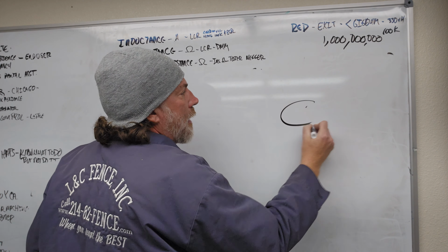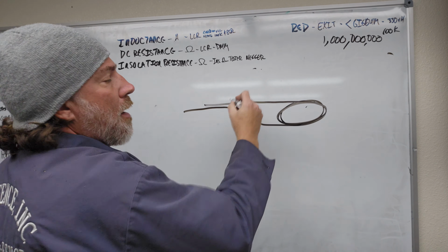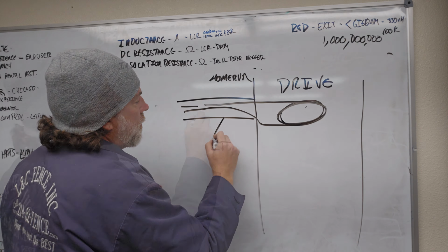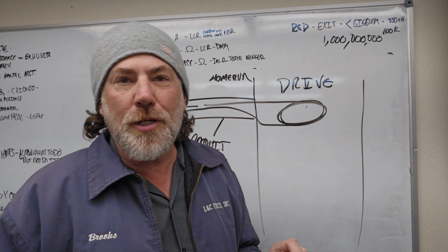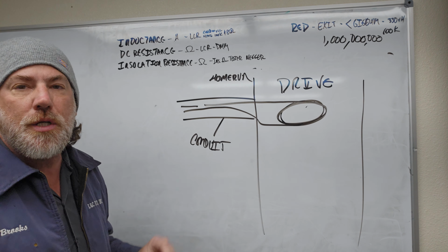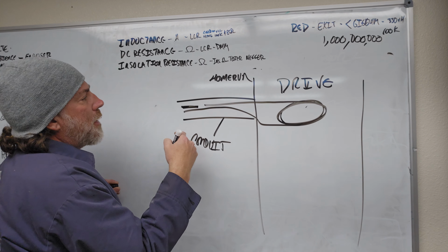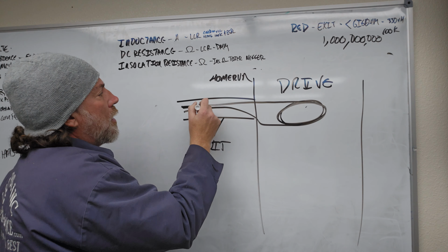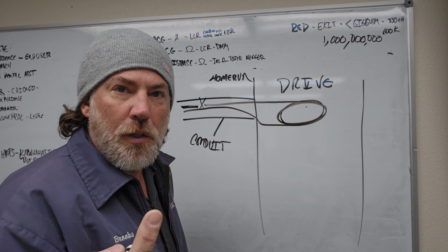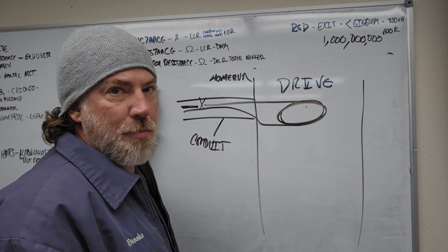So we have a loop in the ground. So we have a coil. That coil comes back. Here's the drive. Here is your home run. Here is conduit. And here's your wire. Insulation is the best it can be in this scenario. All right, do you see where the fault is? So if you test from here, this through the conduit, you could have a break right here. You put your wire generally just on one lead and you test the insulation using an insulation resistance meter, so Megger.